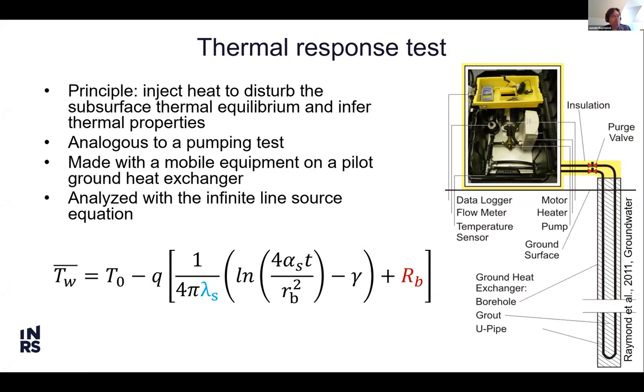Thermal response tests. When we design those systems, we need to know the ground thermal conductivity, right? Because the performance is highly dependent on the ground thermal conductivity. My parameter here, lambda S, for the subsurface thermal conductivity. So we do some in-situ tests before building the whole system. Typically, we're gonna drill one well on site. In this well, we're gonna install a ground heat exchanger. So there's gonna be a pipe installed in the well. And the well is gonna be backfilled such that we have a pilot ground heat exchanger for our first exploration well that is drilled on site.